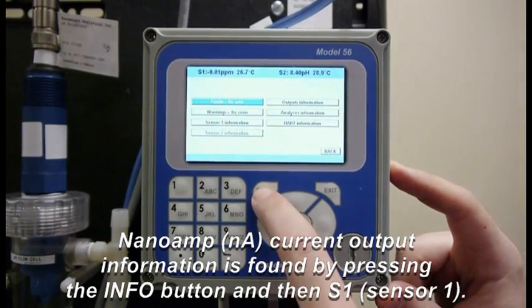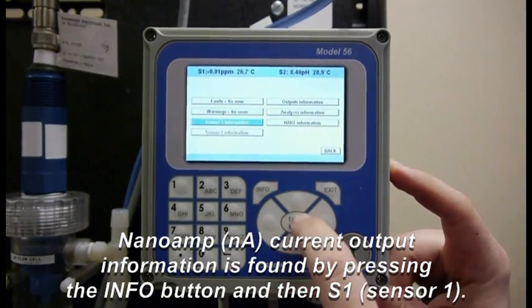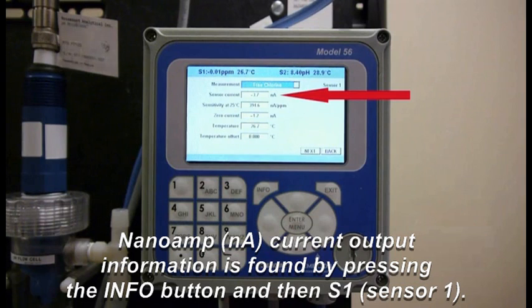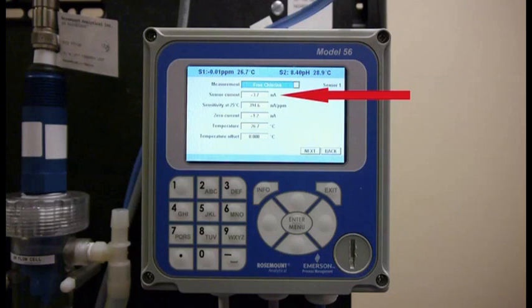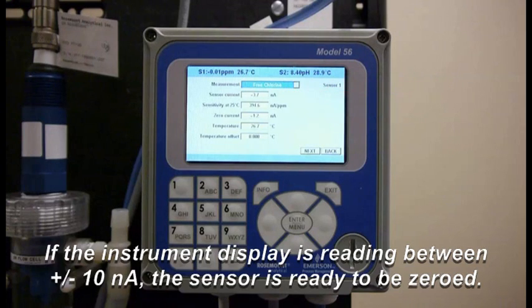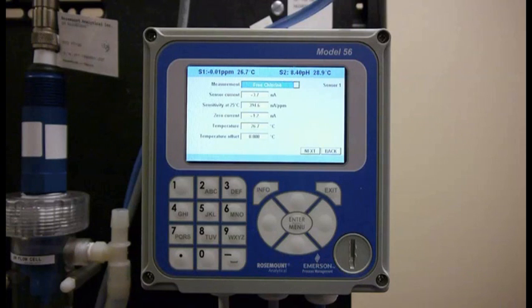You're going to go to Info, you're going to go to Sensor 1, then you're going to need to find the sensor current. It's right now reading at negative 3.7 nanoamps. Here's the second line item on the display. Now the key is it has to be between negative 10 and 10 nanoamps. And it's been stable for quite a while, so I know it's ready to be zeroed.